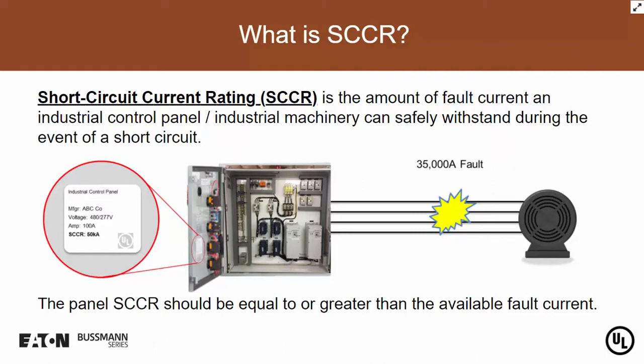Let's start with a discussion focusing on the term short circuit current rating. What we see here on this slide is what I would call a layman's definition of the term short circuit current rating. There is an official definition, and it's found in both the National Electrical Code and NFPA 79. However, what I like to do when I provide training on the concept of short circuit current and how it relates to control panels and machinery, I like to show what I would call a layman's definition, and that's what you see on the screen here. We'll get to the actual, official definition in a few moments, but I think it's easier to see when you read the words what a short circuit current rating is and how to capture it in your mind.